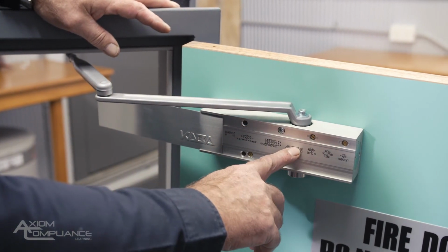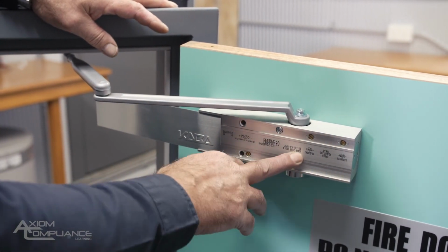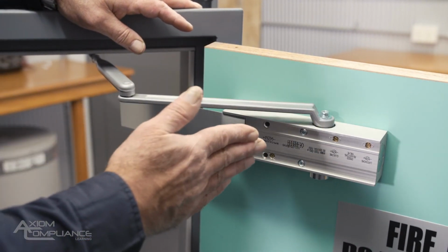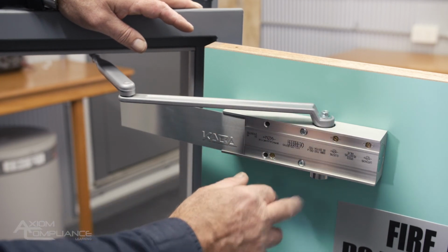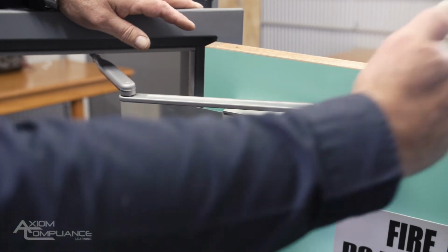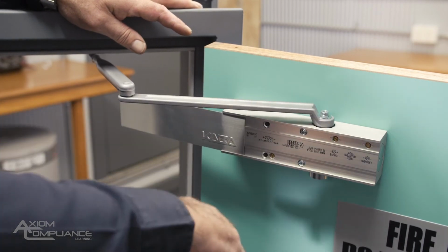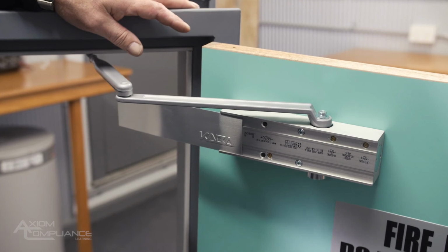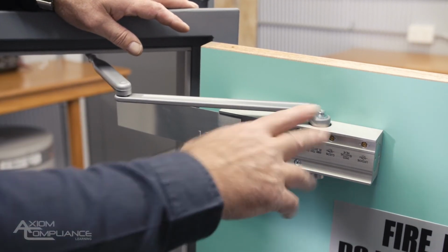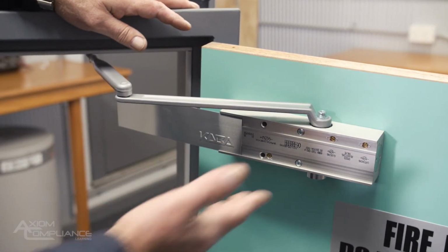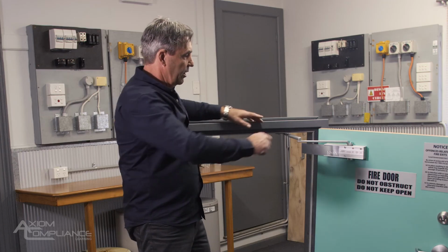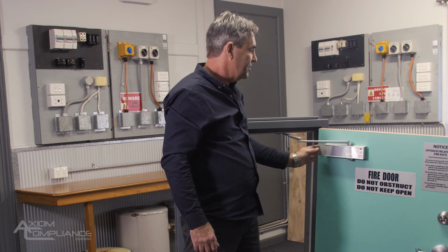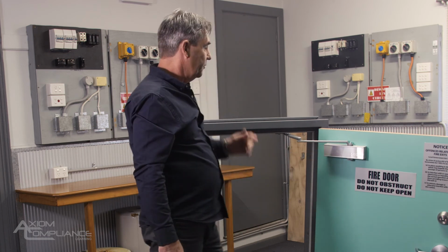And it also gives you some instructions on how you can adjust the closing speed of the door. So you have a latching speed, which was that second part where it actually closes the final closing section, and you have a closing speed. You can adjust it positive or negative. Just use a screwdriver if you feel that the door is not self-closing; you've got to adjust it until it is. If it doesn't work, change the closer. So I've got a plus or minus there. I can increase the tension on the latching or the closing speed of the door if I need to do that.